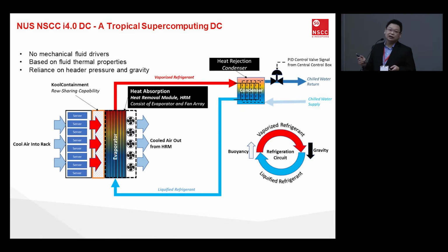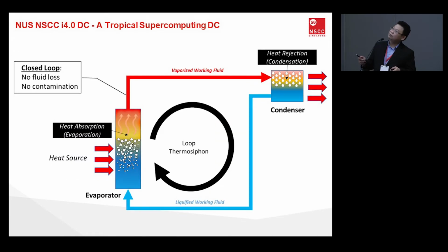So this is a self-generating system. You will notice there are no pumps at all, purely buoyancy and gravity. We don't use any pumps at all. A bit more on this: because it's a closed loop system, there is no fluid loss and no risk of contamination. Everything is closed within the system. Liquid goes in, gets heated up, vaporized, goes here, gets cooled by the chill water, and condenses back.